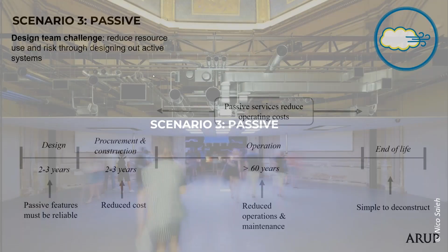For the Marshgate building, we had to start by questioning the brief. Do we need these tight design conditions? Can we relax them? And are the systems going to still be reliable enough for our client? By asking those questions, we were able to remove one floor of plant space, previously dedicated to air handling units providing mechanical ventilation to office spaces and some of the less critical labs, and a significant amount of mechanical cooling, which reduced the electrical capacity to around 55% of the baseline.